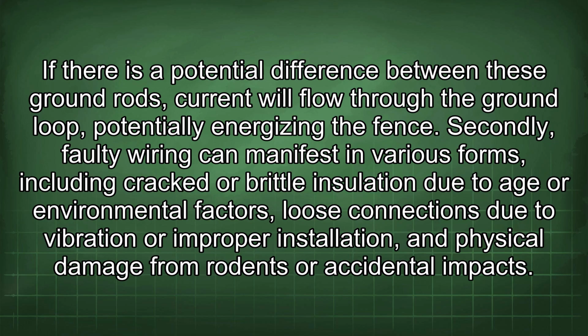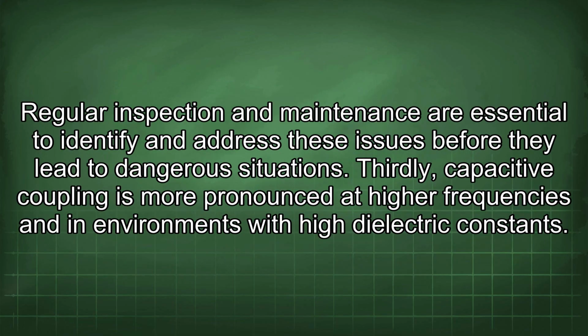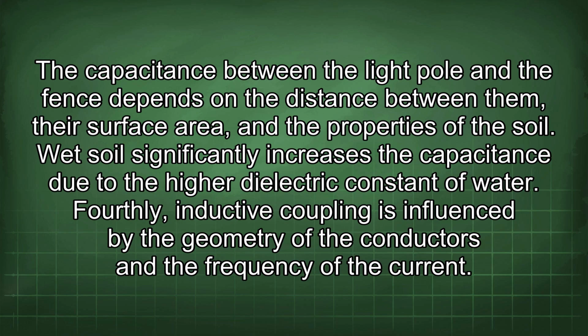Secondly, faulty wiring can manifest in various forms, including cracked or brittle insulation due to age or environmental factors, loose connections due to vibration or improper installation, and physical damage from rodents or accidental impacts. Regular inspection and maintenance are essential to identify and address these issues before they lead to dangerous situations. Thirdly, capacitive coupling is more pronounced at higher frequencies and in environments with high dielectric constants. The capacitance between the light pole and the fence depends on the distance between them, their surface area, and the properties of the soil. Wet soil significantly increases the capacitance due to the higher dielectric constant of water.